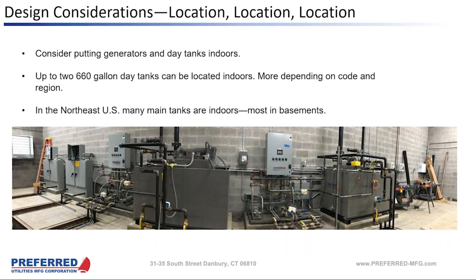Also, that's a starting point here in the Northeast, especially. If for some reason, based on life safety runtime or just the size of the system, you need to have additional storage inside the building up at the generators, we can work with you and with the AHJ to get that approved, whether that's a special case permitted, or we could go to a different UL design. With some hospitals with large amount of storage up at an upper level, we've gone to a UL 2085 on the tank, fire protected. So there are ways to accommodate that on a larger system.